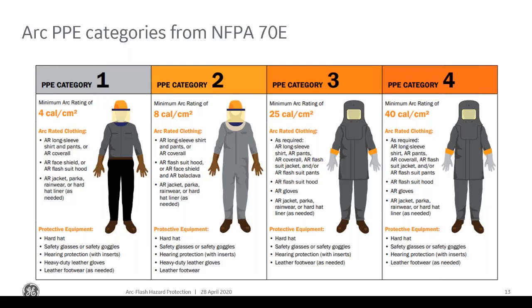And you could see, for very little increase in arc flash energy from a category 2 to category 3, we're talking about going from face shield, helmet, FR overalls, gloves, to something that resembles almost a spacesuit, multiple layers. And it could be quite the production if you need to get into one of these arc flash resistive PPE equipment. So time, cost, downtime, and such can play a big part, besides obviously the risk to personnel.